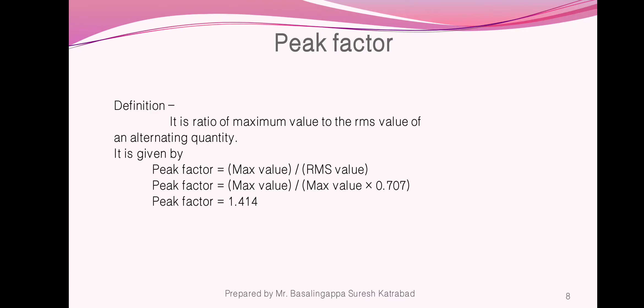Next definition: peak factor. It is the ratio of maximum value to the RMS value of an alternating quantity. Mathematically, peak factor equals maximum value divided by RMS value. Substituting RMS value as V_MAX multiplied by 0.707, the maximum values cancel, giving 1 divided by 0.707, which equals 1.41. Peak factor is used for designing the maximum voltage level, and in insulation designing we use the peak factor to decide the insulation level.